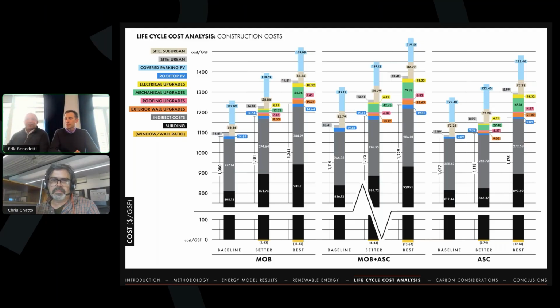When we look at the envelope, it was interesting, because window costs, although increasing going from dual pane to triple pane, the cost per square foot for windows goes up, but because your envelope is decreasing how much window area there is, the cost wasn't linear. The impact to go from baseline to better was about $5 a square foot, and then going from better to best it was only a few dollars more. So you really get a good return on investment for that initial step, and going from better to best is also an increase, but not as much as the first step.